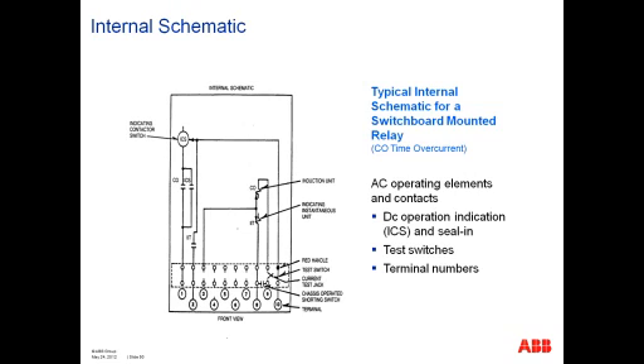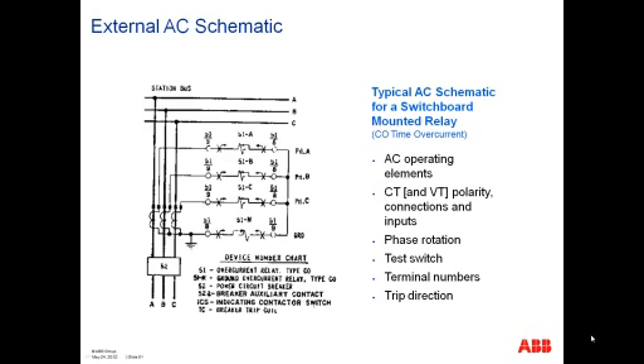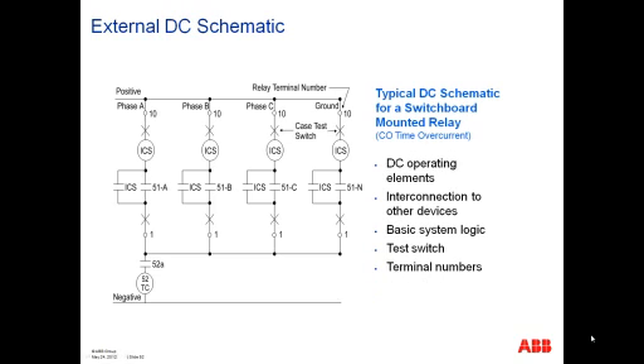And then there's also the legend of the test switch, the current jack, and the terminal numbers. And you have your trip output contacts, and these devices are shown on other diagrams as well. Next. This would be your external schematic showing the connection to the power system, with the terminal markings that show the connection to the actual relay, or the internals of the relay.